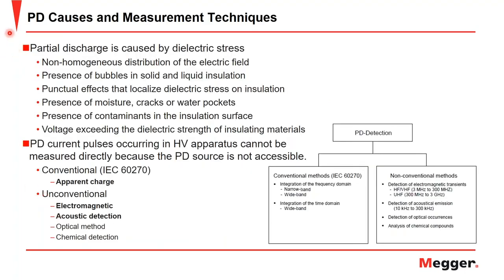Moving on, we have partial discharges, causes and measurement techniques. There are many different ways that partial discharge can be caused, but they all come down to dielectric stress. And this can come in the form of non-homogeneous distribution of electric field, the presence of bubbles in solid and liquid insulation, punctual effects that localize dielectric stress on insulation, presence of moisture, cracks or water pockets. It could be caused by presence of contaminants on the insulation surface, as we saw in the instance of surface discharging, or could be just by the voltage exceeding the dielectric strength of the insulating material.